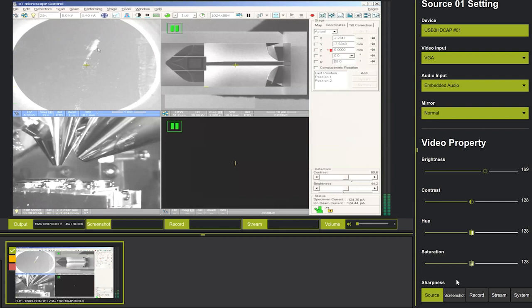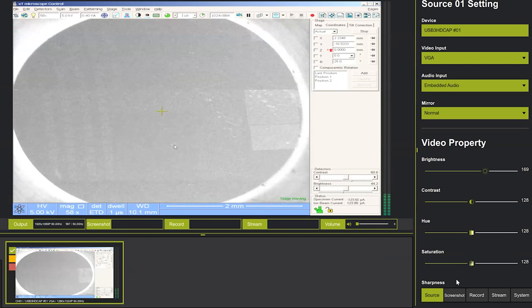So this is the typical UI. Let me explain what we're looking at. The top left window is the electron beam in secondary electron detection mode—this is the typical SEM image. Top right is the ion beam image, meaning ion beam in, secondary electron out. I don't have a detector to detect secondary ions, so what I'm detecting is secondary electrons using the same detector for both of the top two images. It's always the same; I have to find the sample.